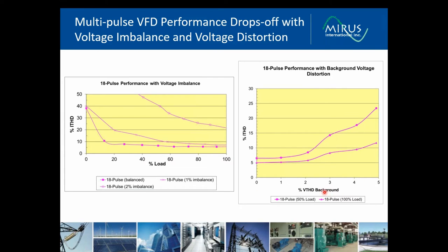In this graph on the right, we've got background voltage distortion. We start with zero voltage distortion, which basically doesn't exist in our power system, so this was slightly more than 0% when we were doing the test. But then we went up from 1% all the way up to 5%, and we did this by adding variable speed drives in our test facility to create the voltage distortion. This lower graph is operation under full load, 100% load, so you can see, again, quite good performance with very little background voltage distortion, but as we approached even the 5% level, we were well above 10%. And at 50% loading, the performance drop-off is even more dramatic. So both of these conditions are very common in marine applications and therefore often make multipulse or phase-shifting strategies ineffective.